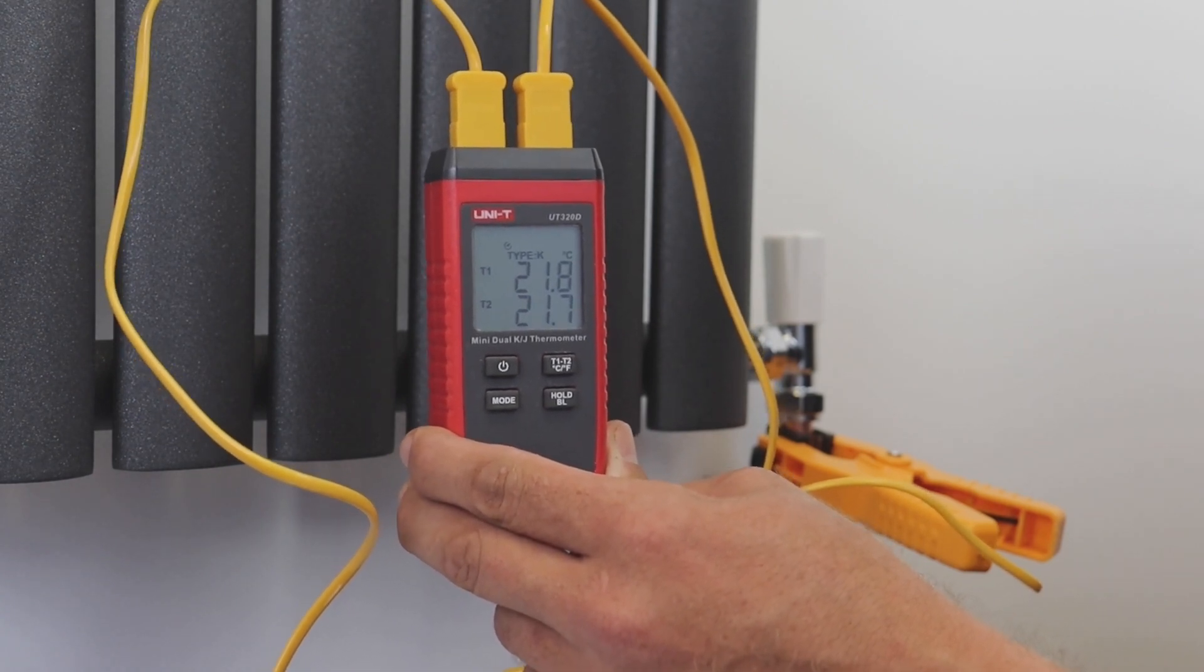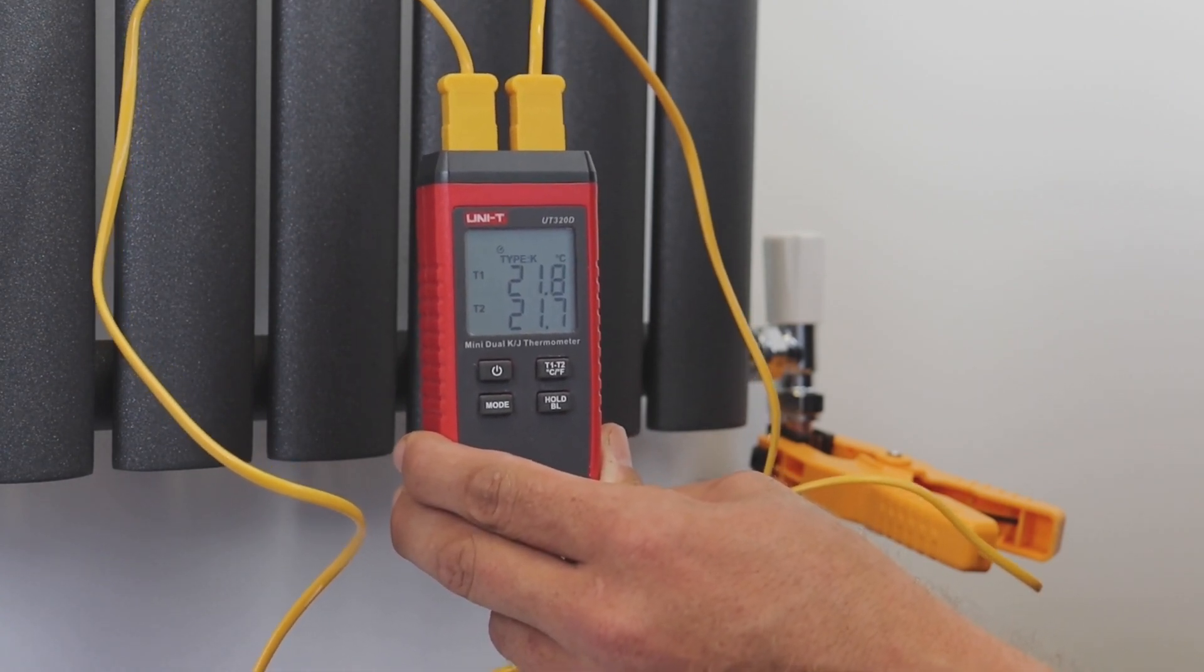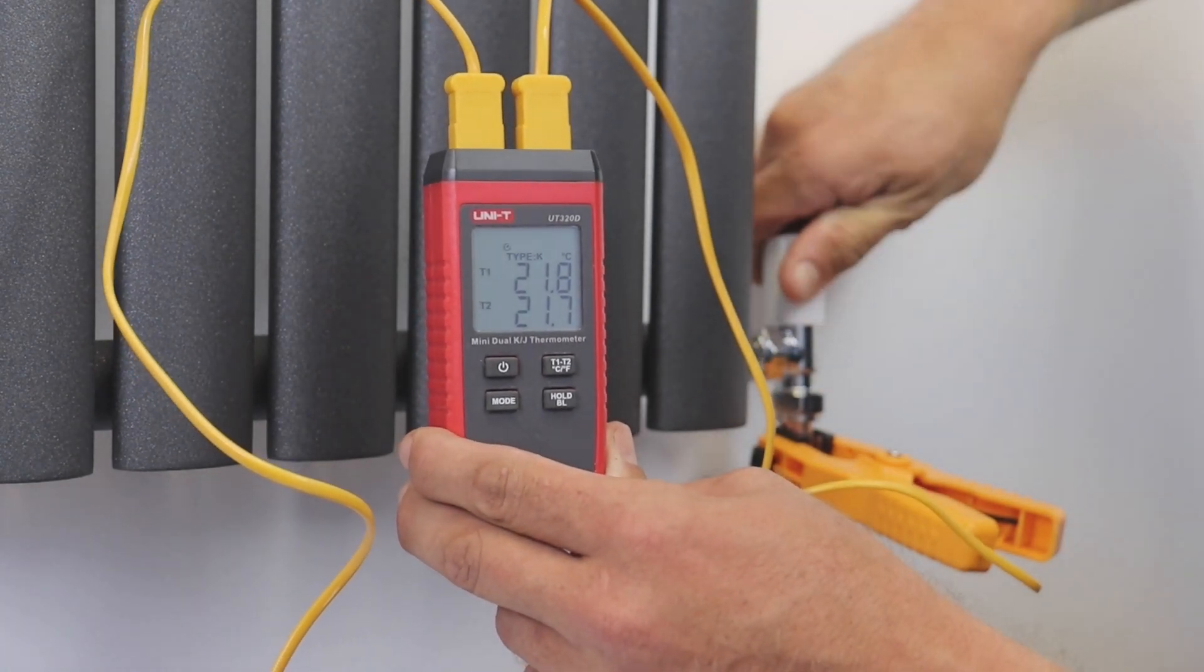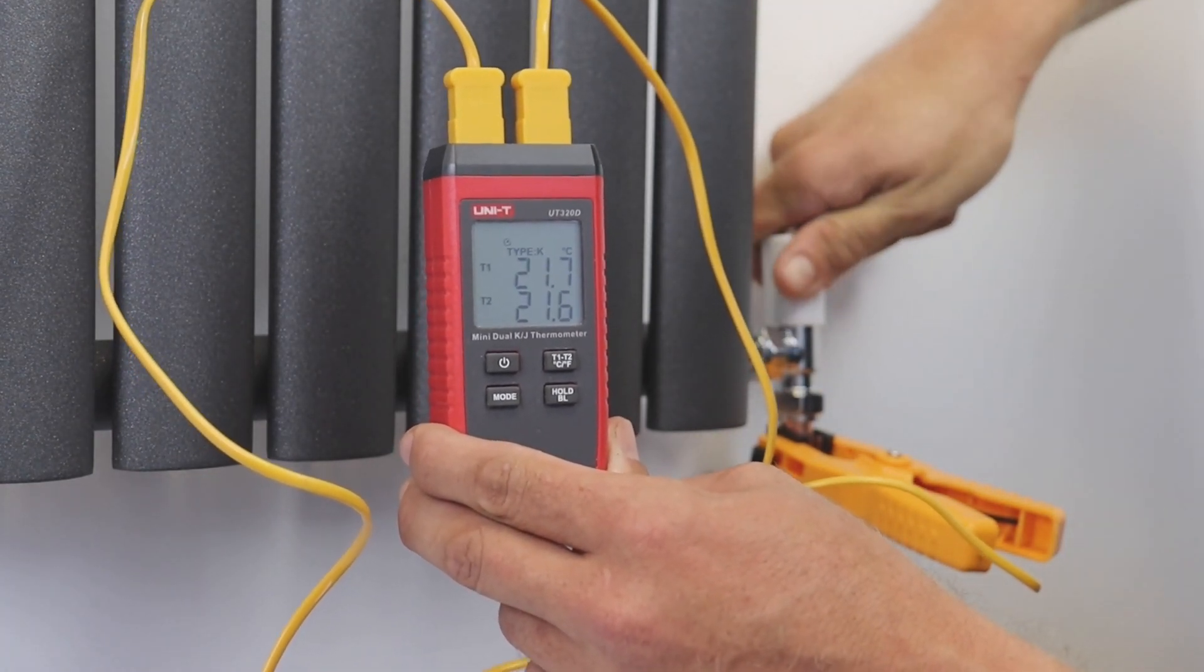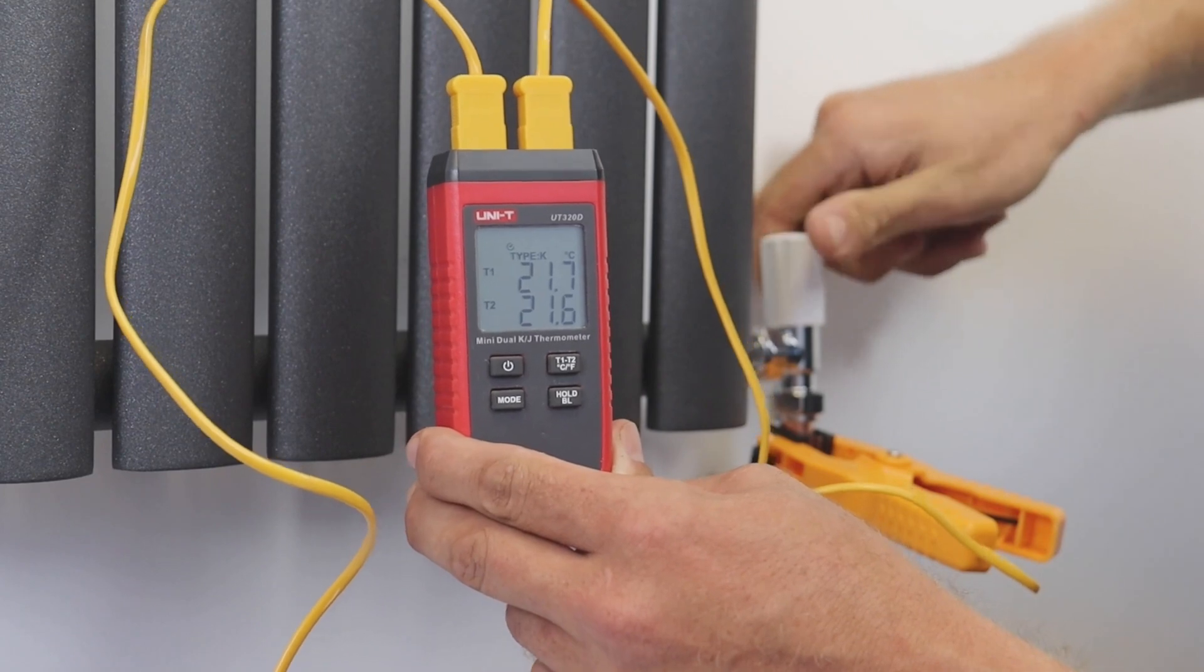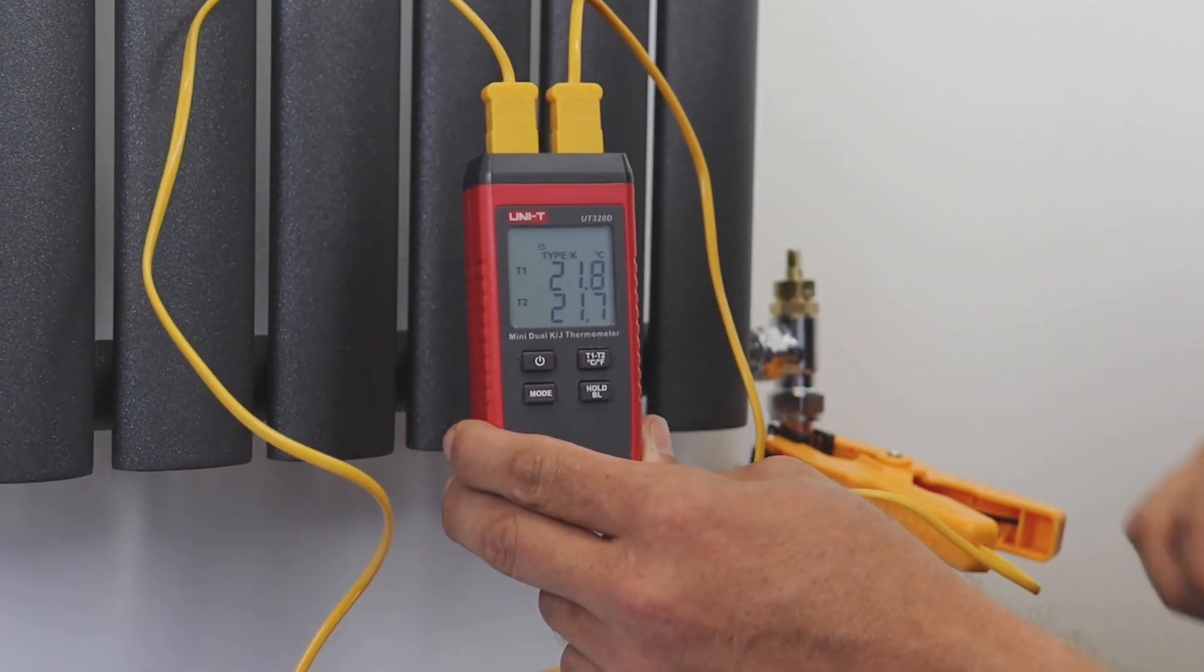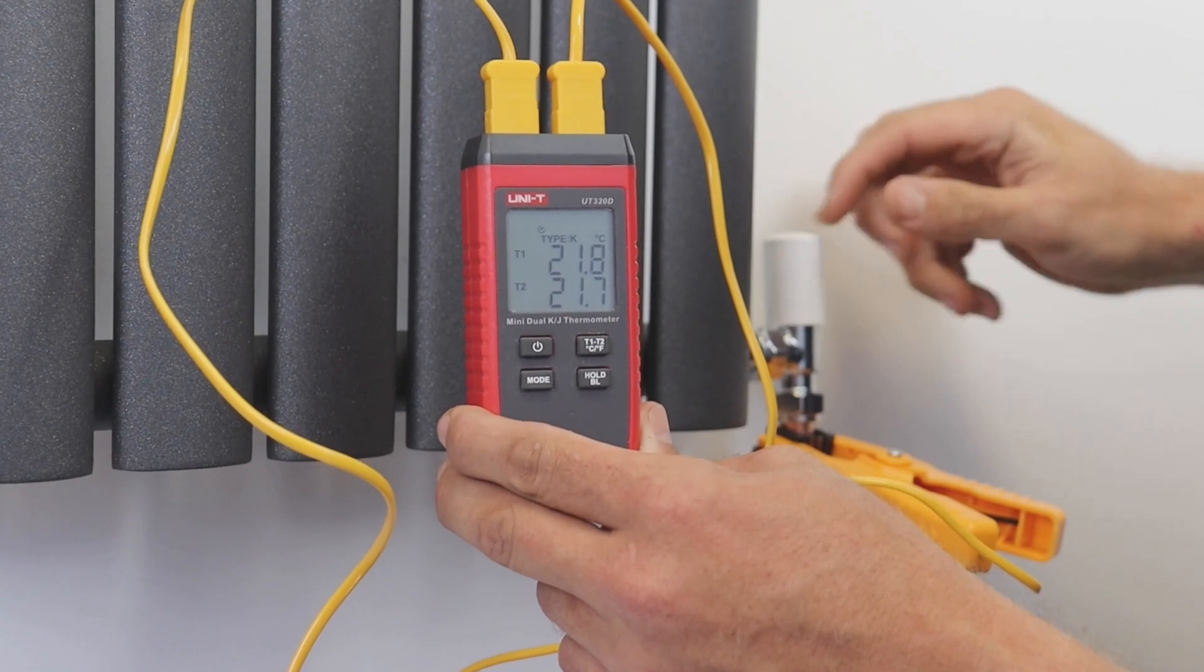We need this to typically be between 10 and 20 degrees depending on the boiler manufacturer's specification. The way we get to that is we use the cap on the lock shield to turn the lock shield down until we get that difference. Once we're there we swap the caps out from the adjusting cap to the locking cap, pop the screw down, and that radiator is then balanced using the lock shield.